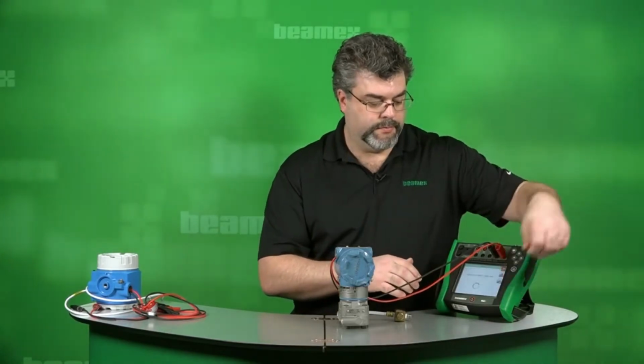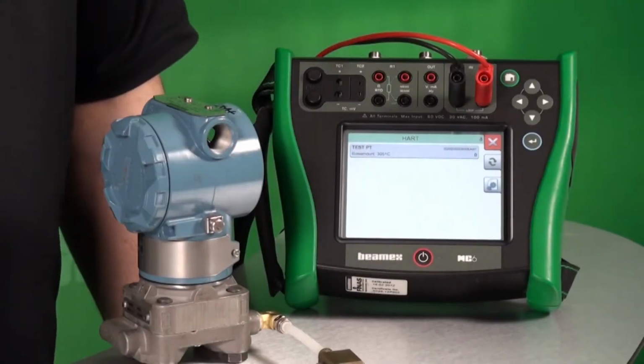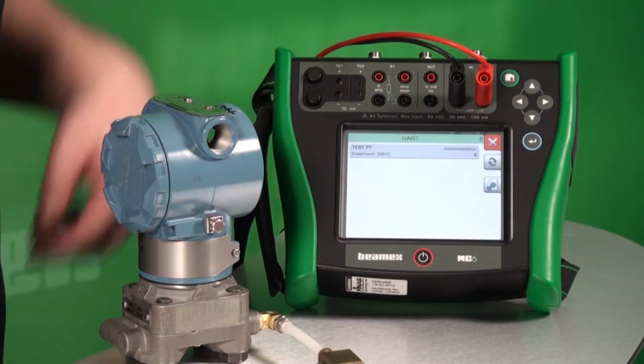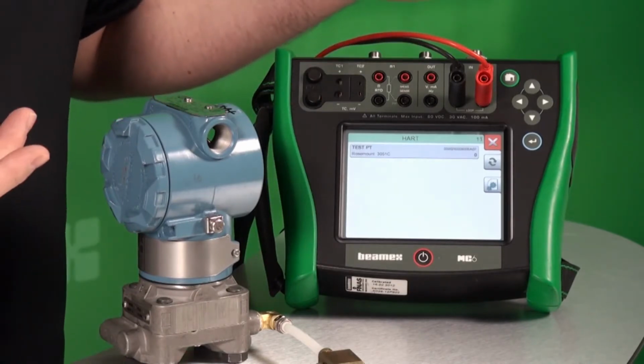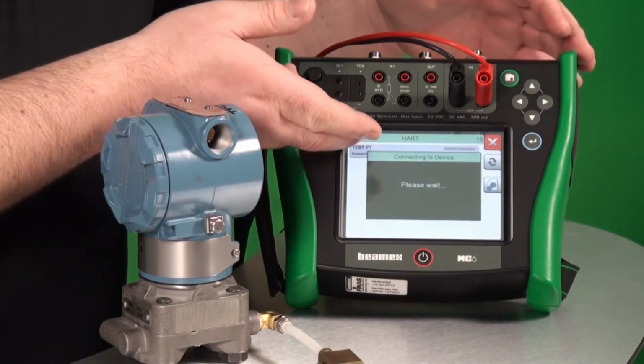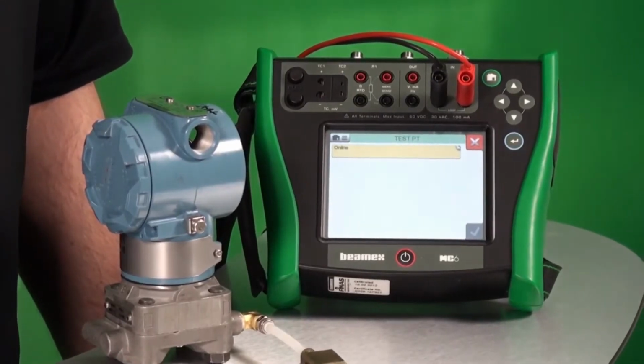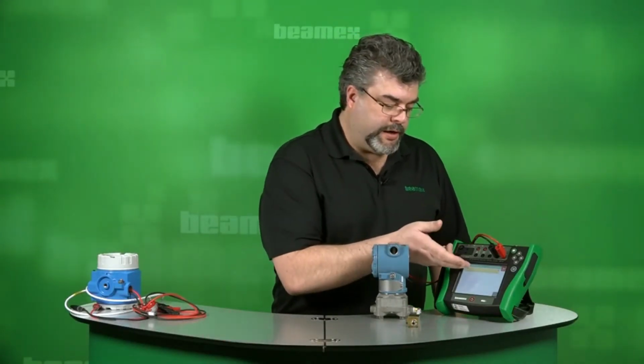And press check. The communicator has started. It's found our device, which is actually called Test PT. This happens to be a Rosemount 3051C. We just press on it to enter the DD structure. What you're seeing is a representation of that DD structure. If we hit online, we can go down to the next level.